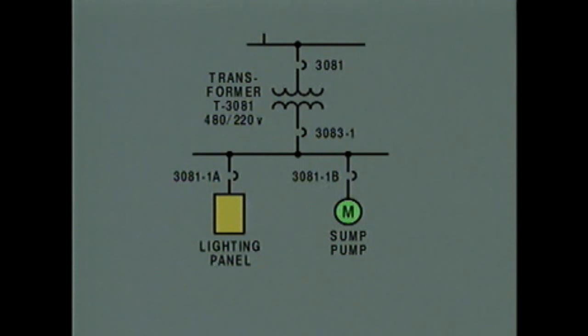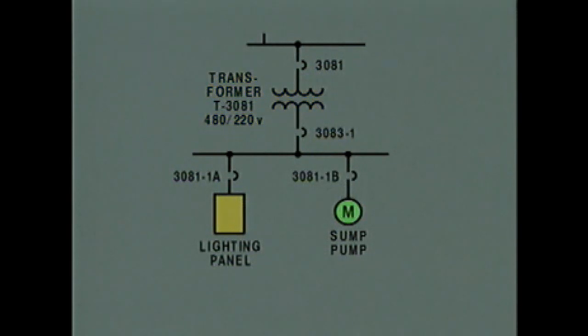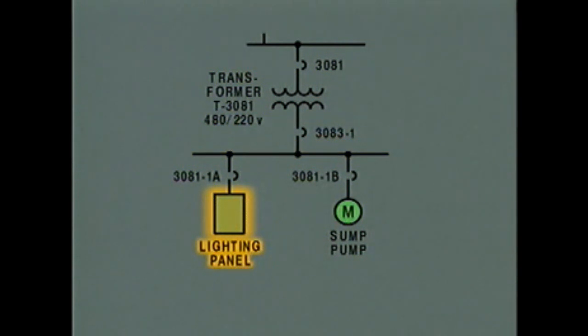After the circuit breaker, power passes through a power transformer. A power transformer converts the relatively high voltage from the load center to a lower voltage for the equipment fed by the circuit — in this case, the transformer changes the voltage from 480 volts to 220 volts. From the power transformer, power flows through another circuit breaker and then to a circuit that supplies a lighting panel, which supplies power to several lighting circuits, and to a sump pump motor.